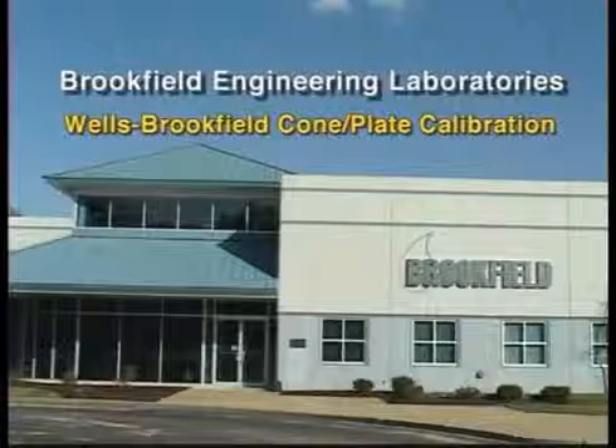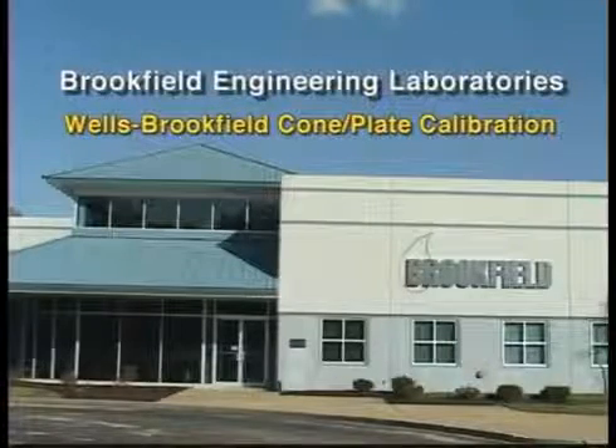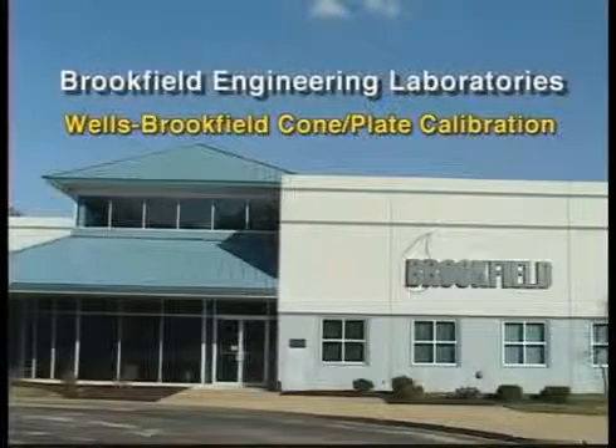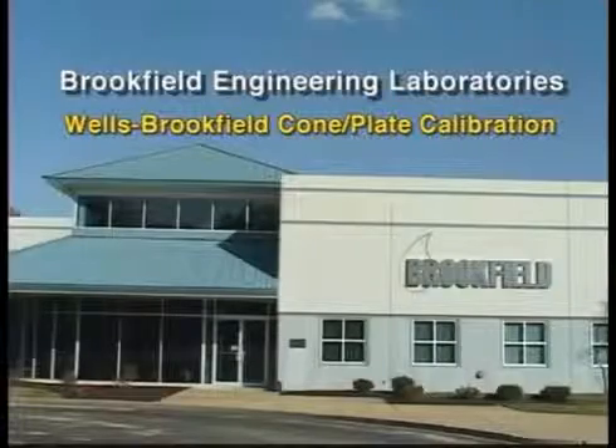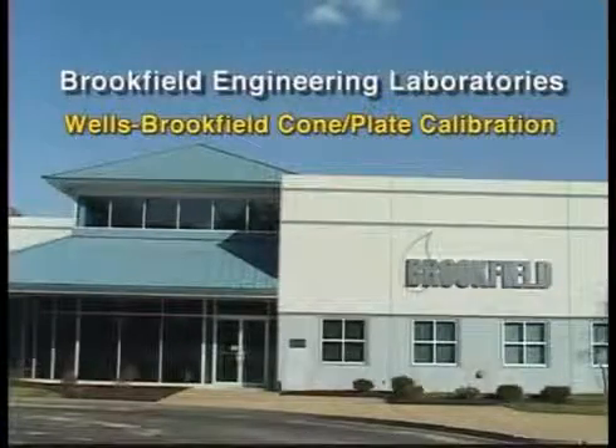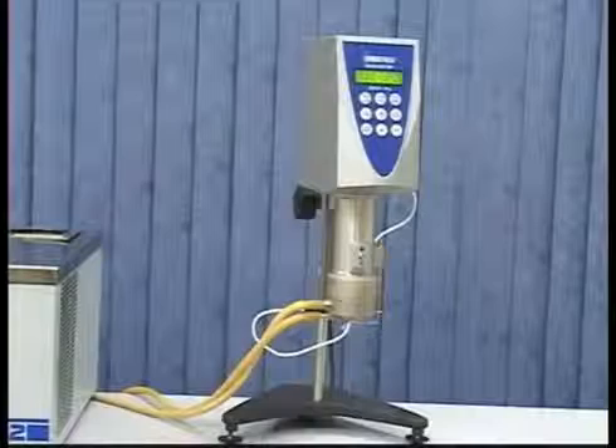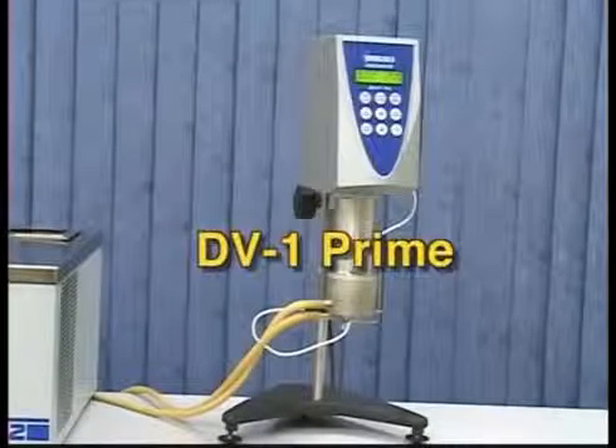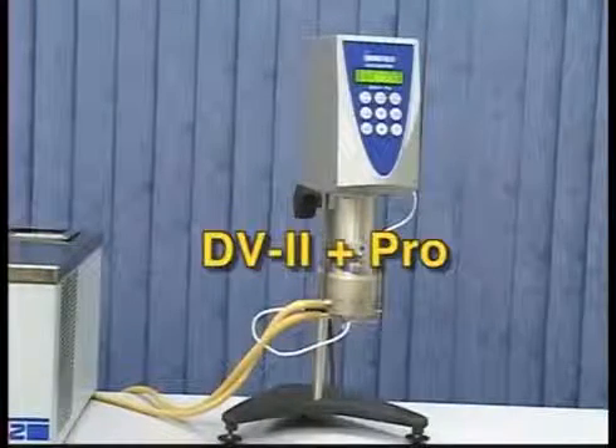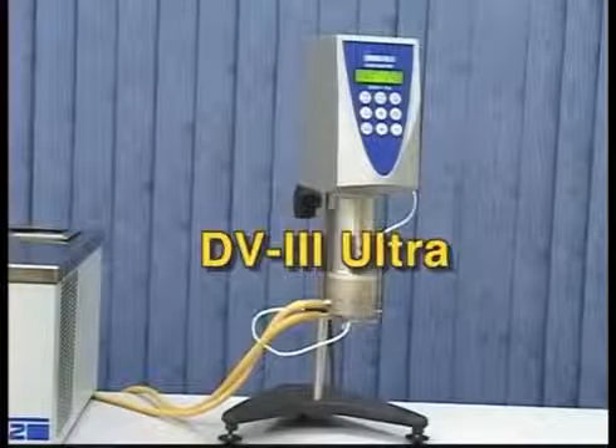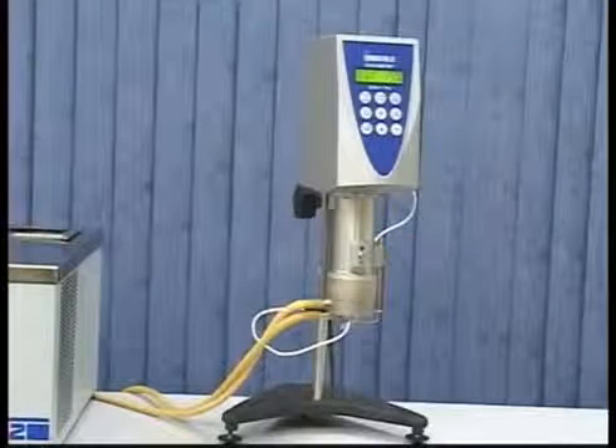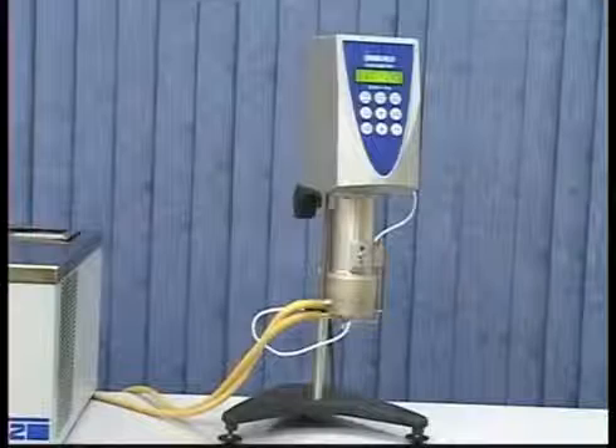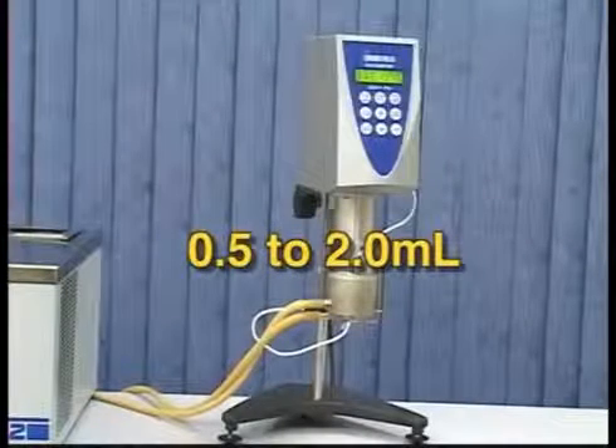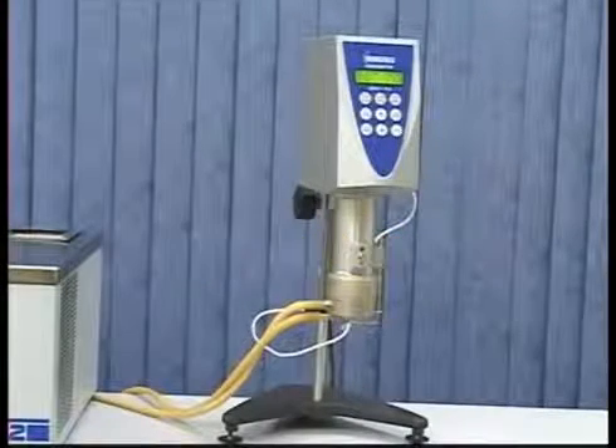This video will show how to set the gap and the proper calibration routine recommended by Brookfield Engineering for our Wells-Brookfield cone plate viscometer. The Wells-Brookfield cone plate is an option available for the DV1 Prime, DV2 Plus Pro, and DV3 Ultra instruments. This configuration is for testing small sample amounts of 0.5 to 2.0 milliliters.